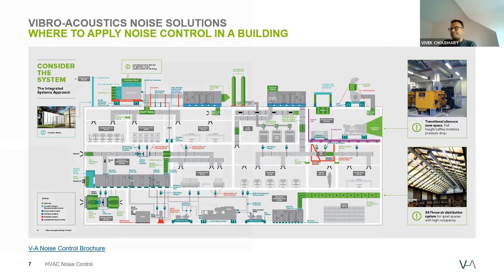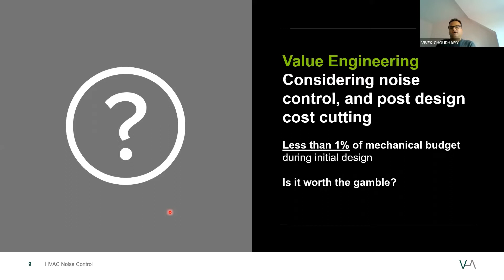So why do noise control problems exist? Basically, someone may design noise control from a consultant's point of view, but then it gets value engineered out. Is it actually worth it? The noise control solution is less than 1% of the mechanical budget of the total project cost. But if there's an issue down the road after it's been VE'd out, it ends up costing 5 to 10 times more, because we have to take the ductwork apart, put the noise control solution in, and redo the whole ductwork again.